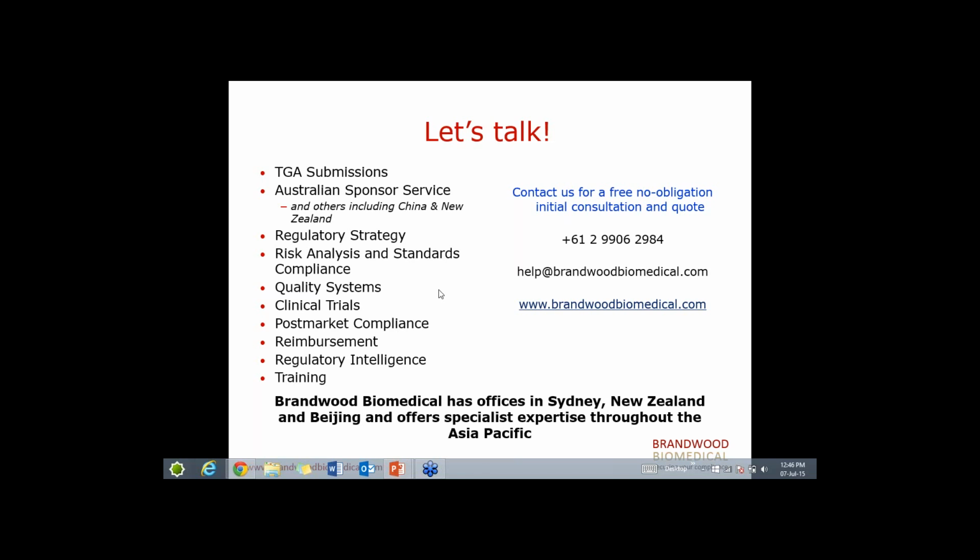Okay, there's one that says, what is the length of time for technical file review? For devices, if you're registering a product based on CE certification, there's actually no re-review of the technical file. As long as the annual fees are paid and the notified body is undergoing these reviews, you don't actually need to do anything with TGA. However, once the notified body does review the technical file, they will usually reissue a CE certificate, especially if it expires, and that must be notified to TGA by means of a variation to manufacturer's evidence. For some high-risk classes, this can actually trigger another application audit if there's an expired CE certificate sitting on file for a particular device.